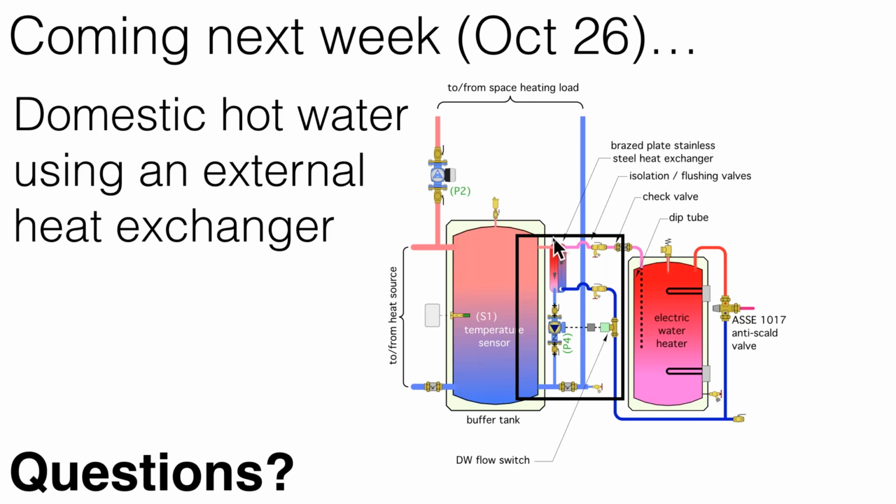Perfect. And then Ron actually wanted to know, since you use the same supply water temperature, did you account for temperature drop in your radiant loop runs, or was it insignificant? Yeah. I haven't actually measured it, but we're looking at temperature drops probably in a range of about 15 degrees at design load on our radiant circuits, and across our radiators. Now, you don't have to have exactly the same temperature drop. Essentially, you focus on your supply water temperature.